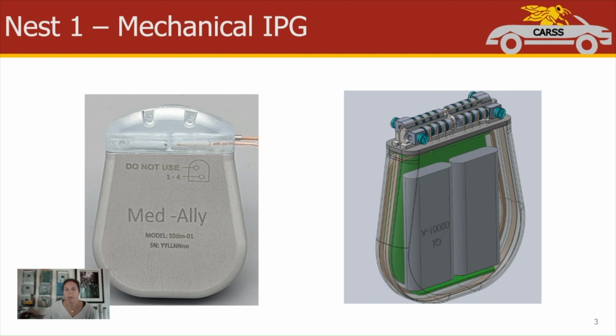A hermetic enclosure will be made primarily of a grade of titanium that will be laser welded together to form a hermetic barrier and was selected to facilitate charging without overheating the IPG during the charging once implanted. The titanium case can also be marked with any pertinent labeling and identification that is desired or required by regulatory authorities. The IPG header has 4 lead access points, each with 4 ball seal IS4 contacts or 2 8-contact leads. Additionally, there are 4 sets of set screws to secure the leads in the header and 2 locations for suturing the IPG to underlying tissue. Additionally, Nest 1 includes an external charger that accompanies an IPG.